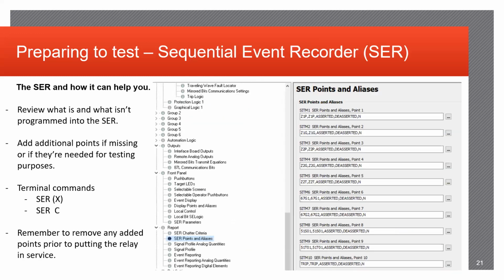Going back to your test prep, the SER stands for Sequential Event Recorder. This is data that may be associated with any elements that you may be testing. It's pretty much an event recorder of sorts for testing purposes and also in service purposes as well. So for testing purposes, the SER is extremely important to use for proving elements pickup when need be.